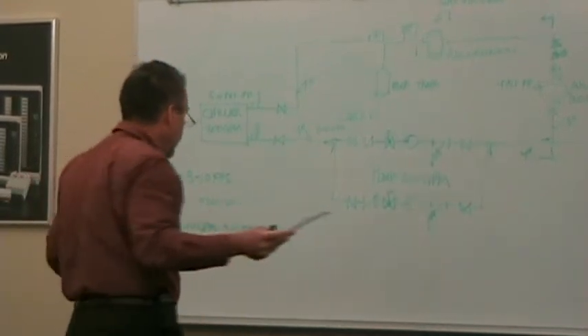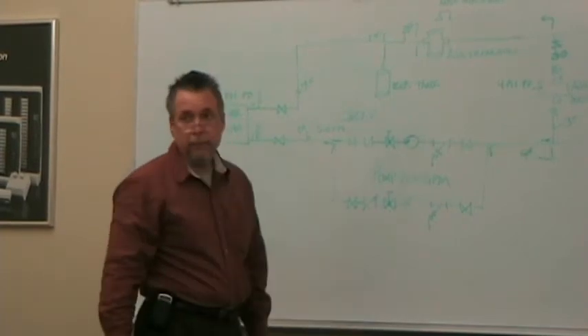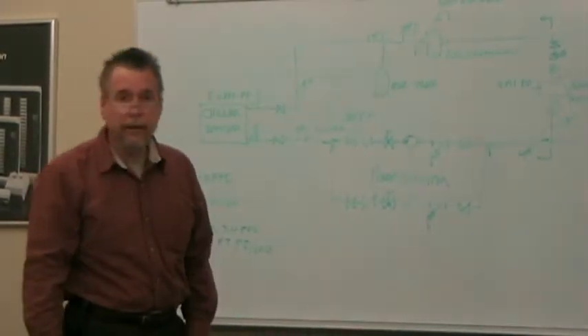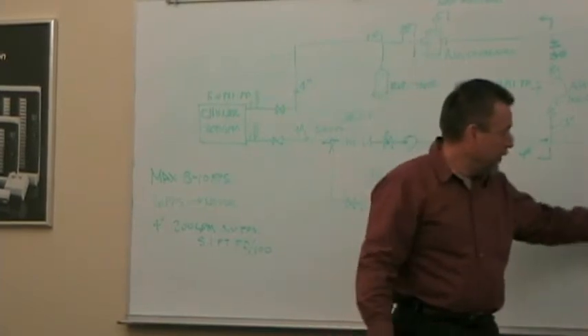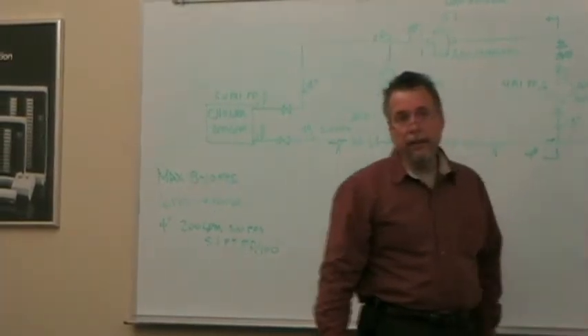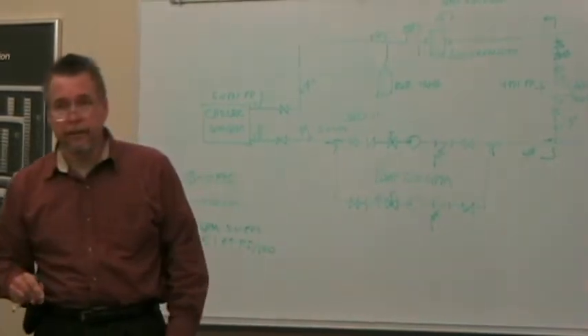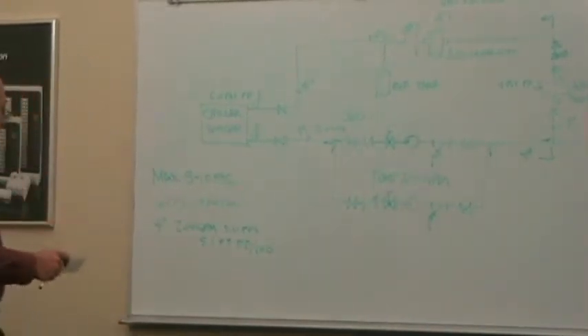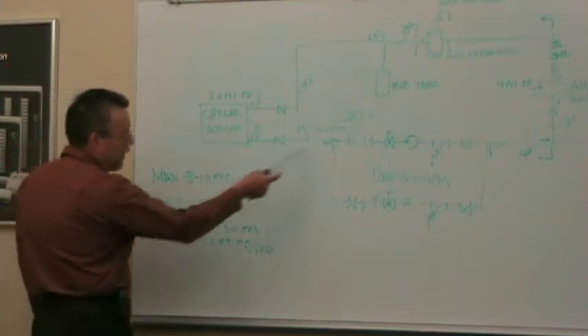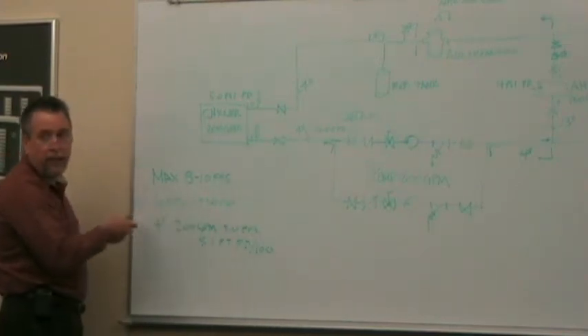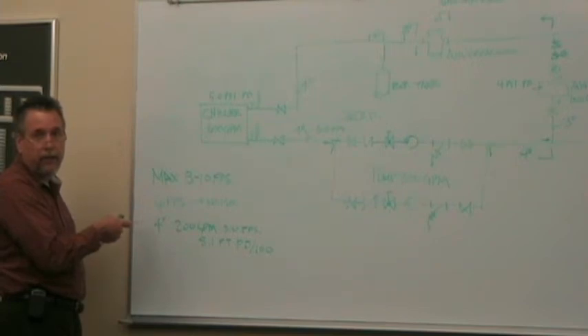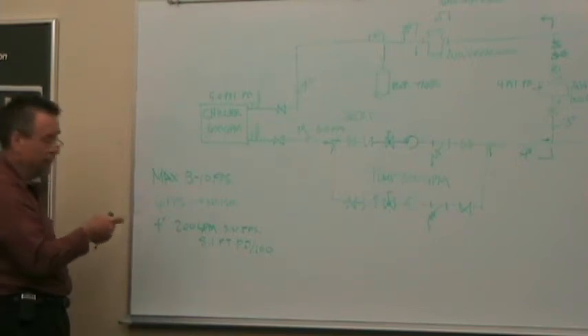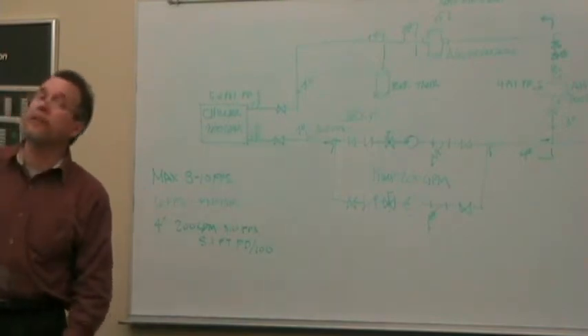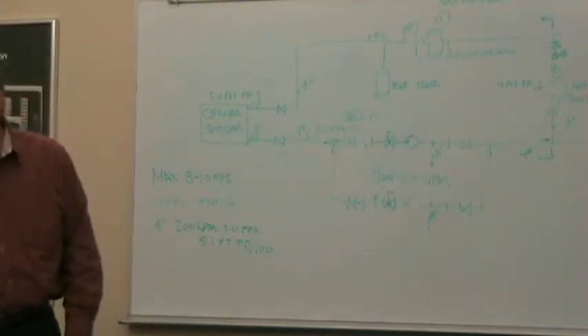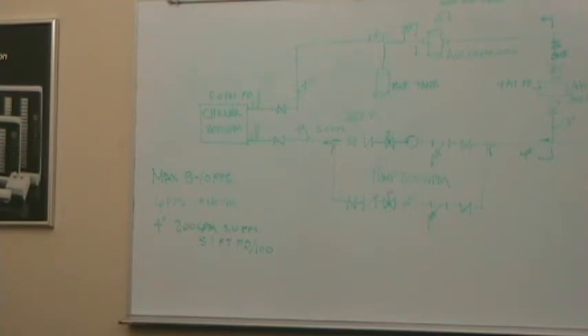Now, what I could do, I said, well, I might save some money. I might go to a 3-inch pipe because my pipe has very little pressure drop. But what happens, all these things start going up too. The 3-inch check valve, 3-inch strainer. And so I'm really sizing that pipe on future capacity, so that the CEO or the guy in the office that has that 4-inch pipe run across the ceiling, which is a bad idea anyway, doesn't call and say, I hear something. Question, he also says that pipe for like a few years down the road when the pipe starts getting kind of filled in.